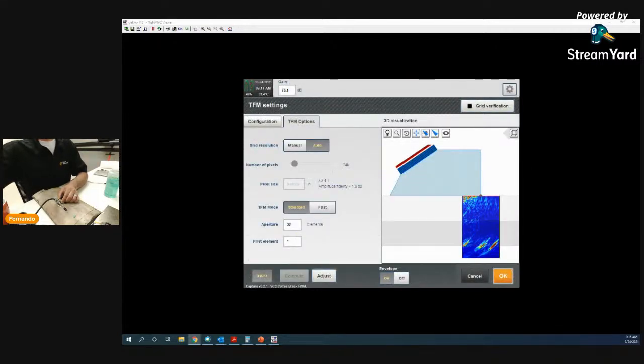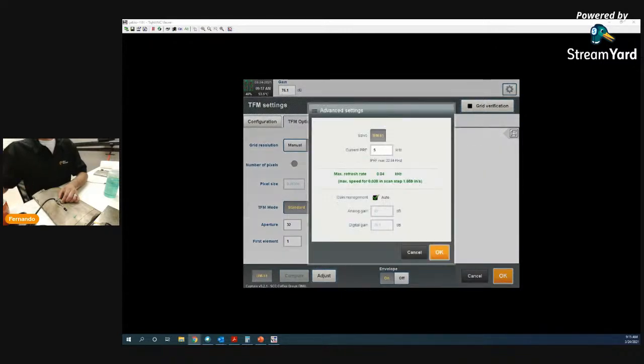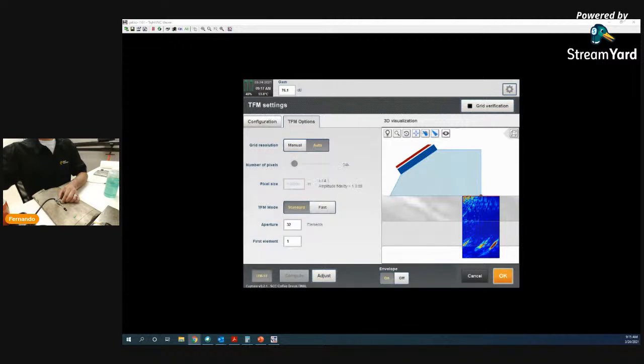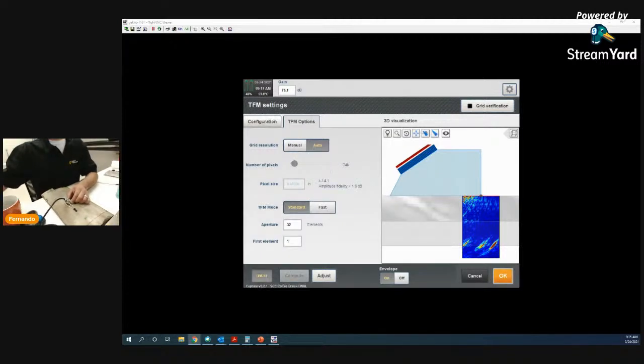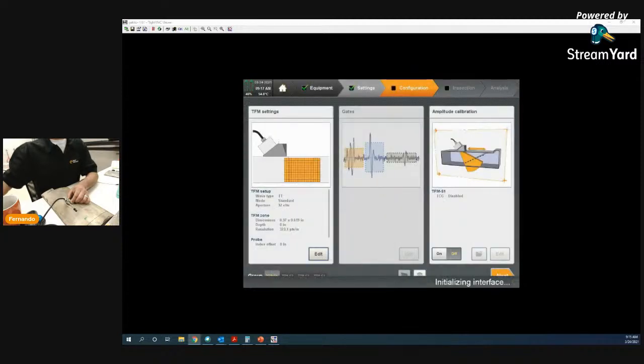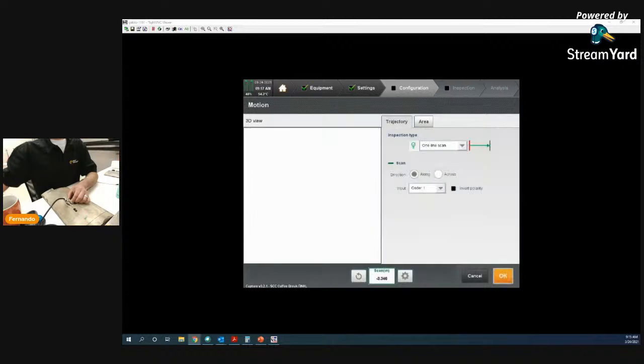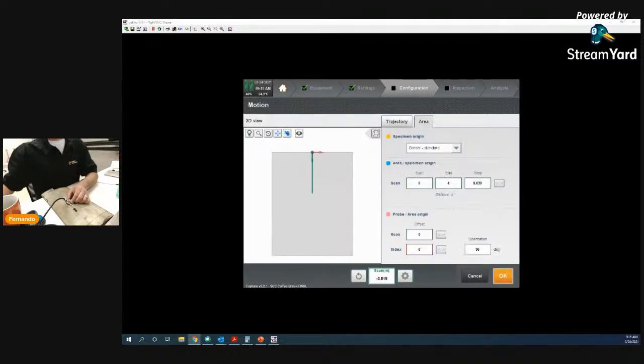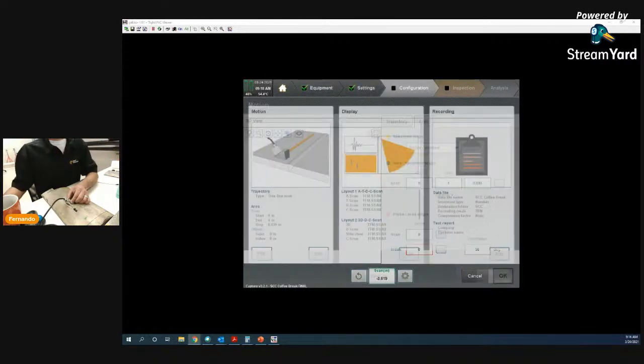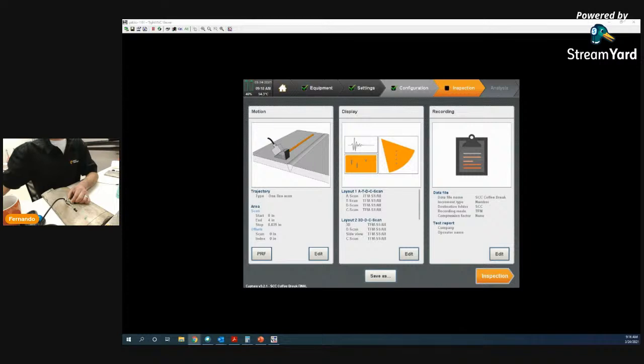If I go to TFM options, there is a fast option where if you want to go faster, if I hit this icon up here, it's going to tell me that the maximum scan speed is going to be 1.6 inches. So you can do that to see if you can increase the scan speed. You can see here, the number of pixels that I have is going to be 24,000 for that area of interest. So I hit next, edit. Right now I'm doing a one-line scan because I'm using the encoder. The scan area is going to be 4 inches. I'm going to start at 0, scan end is going to be 4, and the step is going to be 0.039. So it's going to record every 0.039. It's going to take a slice of data.